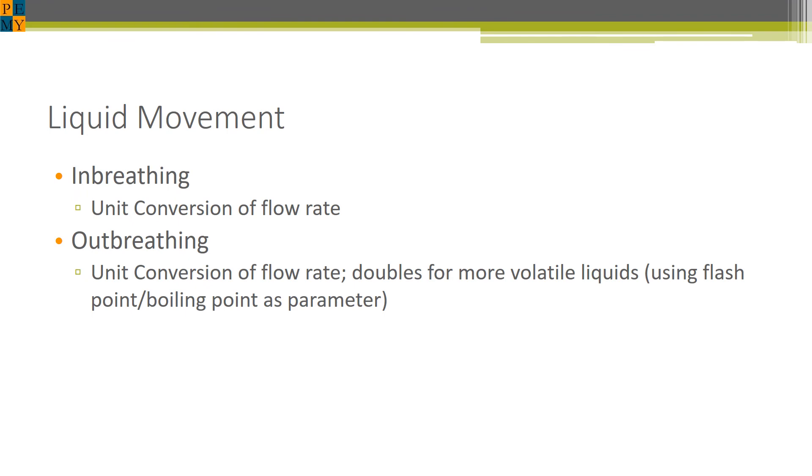Similar to the main body of API 2000, Annex A for liquid movement into and out of the tank uses a direct unit conversion of the flow rate to determine the venting requirements. Also similar to the main body, for outbreathing, the unit conversion rate is actually double for volatile liquids. Unlike the main body, which uses vapor pressure to determine whether a product is considered volatile or not, Annex A uses the flash point, which may not be as accurate, but was considered acceptable and a good enough approximation to determine whether a product was volatile or not.